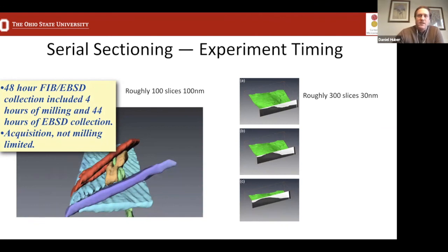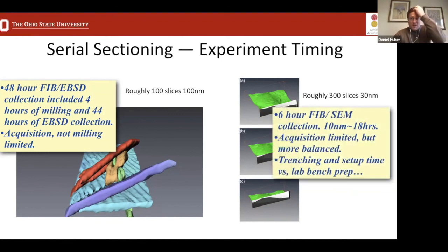And there's the trick that when we're using lower beam currents for, say, serial sectioning, trying to remove 10 nanometer or 30 nanometer slices, you want to use a lower beam current, and at the smaller beam currents, that's where the source is sharper and brighter with the gallium FIB. So there's pluses and minuses to both systems.